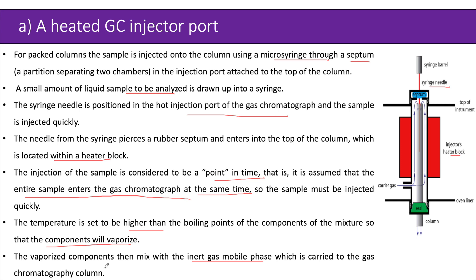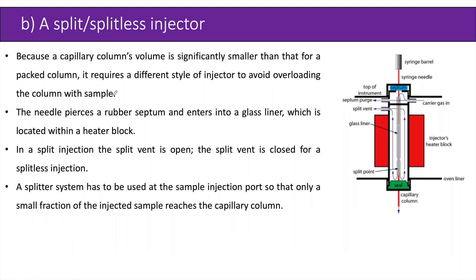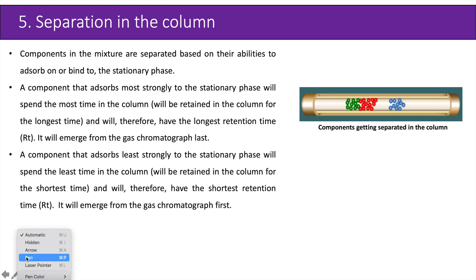Another injector system is the split/splitless injector. Because the capillary column's volume is significantly smaller than that for a packed column, it requires a different style of injector to avoid overloading the column with sample. The needle pierces a rubber septum and enters a glass liner within a heater block. In a split injection, the split vent is open; for a splitless injection, the split vent is closed. A splitter system ensures that only a small fraction of the injected sample reaches the capillary column.